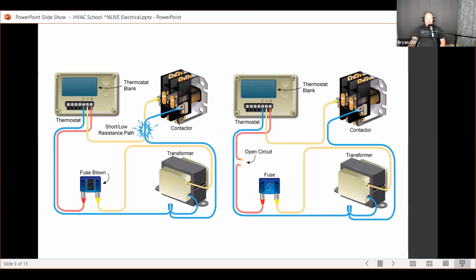Francisco says, Bryan, I have a question regarding fuses. I have a 30 amp fuse at 500 volts on a 3-phase compressor. I've asked several people and still don't know if anything above 500 volts will also blow the fuse, or only an over-amp situation. I normally see 600 volt rated fuses.